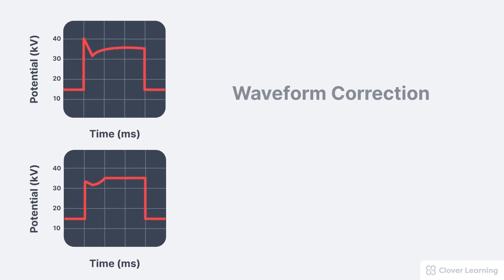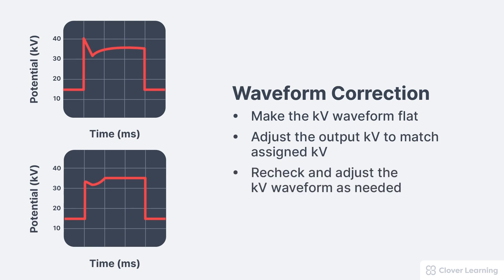An incorrect KV waveform must be corrected. The KV waveform at the generator affects the KV output at the tube. To fix this, we start by making sure the KV waveform is flat. Next, adjust the output KV to match the assigned KV. Finally, recheck the KV waveform and adjust as needed. Continue back and forth until both the waveform and the output are correct.